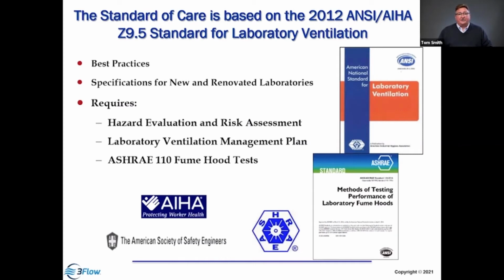And it requires that all facilities have a hazard and risk assessment, a lab ventilation management plan, and that they're conducting ASHRAE 110 hood tests. So this standard sets the basis for the criteria for determining whether hoods function properly.